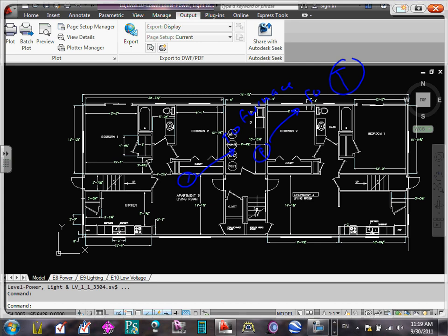Any questions, guys, about the heating? How do we power it? It's powered directly from the furnace, so we don't have to worry about powering it. Any questions about that? What symbol to use? A circle with the T inside it. I think we have it; if we don't have it, create it. And just a loop like this that says "to furnace, to thermostat". And the size of the wire, either you write it on it or you keynote at the bottom: all thermostat wires shall be 18/4.